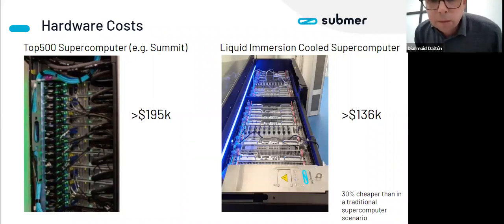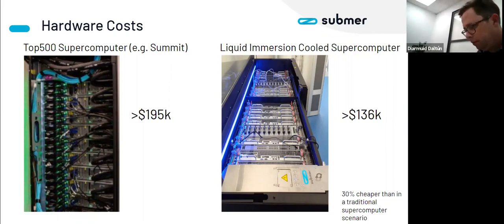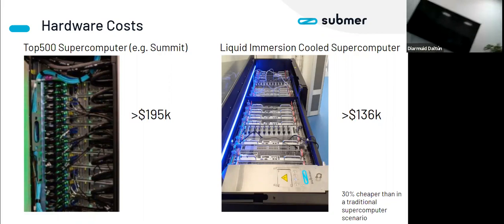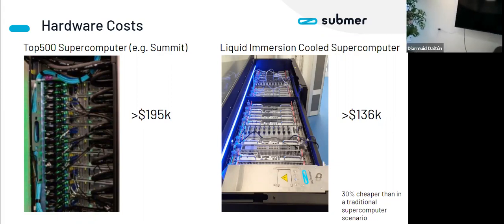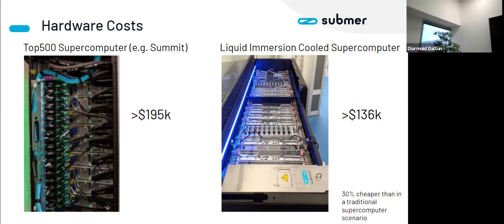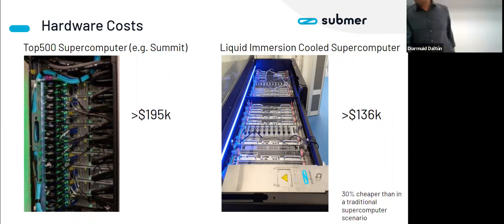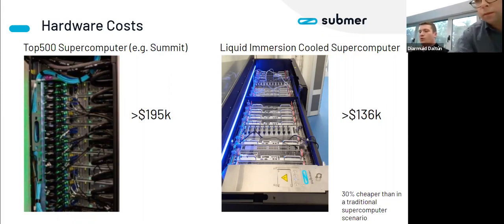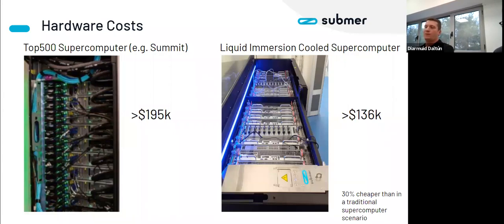When you take a node that was designed for air cooling and put it into immersion cooling, the first thing you realize is that you can remove a lot of components that you originally put in there. That includes replacing high-grade, high-end heat sinks with cheaper heat sinks. Obviously, we would completely remove any type of direct-to-liquid cooling components, which are deployed in these specific IBM nodes, and a lot of the air handling components that exist inside the server are also removed.